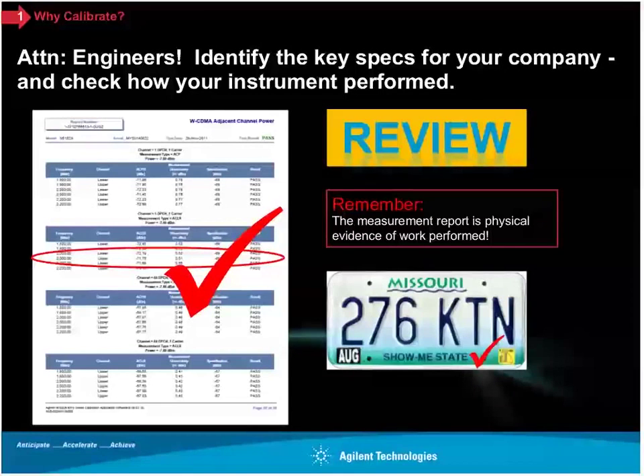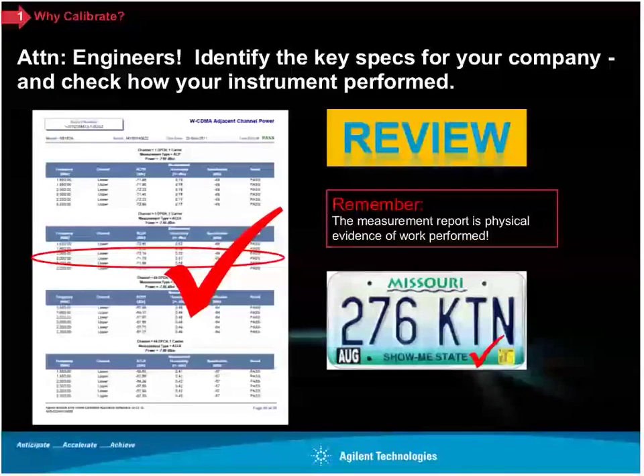When it comes to calibrations, I think everybody should be from Missouri. In other words, the cal provider should show you all the measurements that they made so that you can do a review of those. And in particular, the best, most important ones to review are those specifications, or how did the instrument perform at the calibration event for those specifications that your company really relies on.